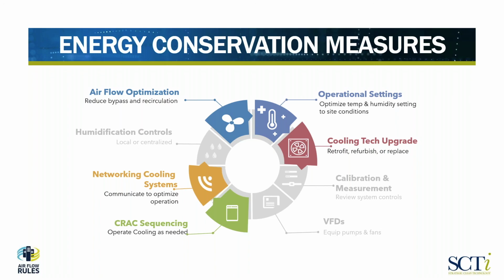So going back to airflow optimization, it's a bit of an iterative process that we go through here. Airflow management is a single stage: you go in and put in blanking panels, cold aisle or hot aisle containment, maybe some additional perforated tiles. That's all part of airflow management. But once we've gone through and used the rest of the appropriate tools from our toolkit, we go back and do airflow optimization, meaning given I've improved the management of the air and the temperature, how much can I dial down the airflow at that site and optimize the amount of air delivered to the IT equipment.